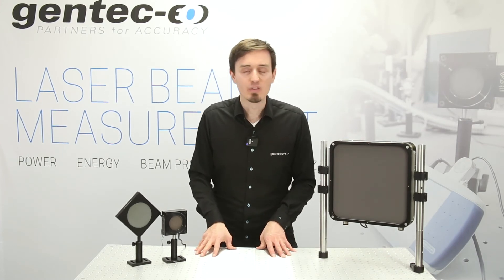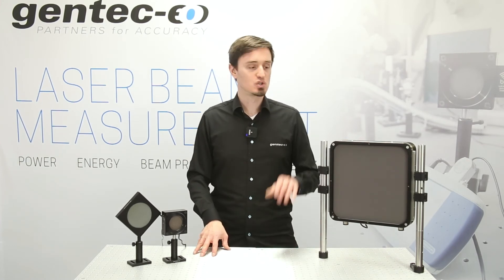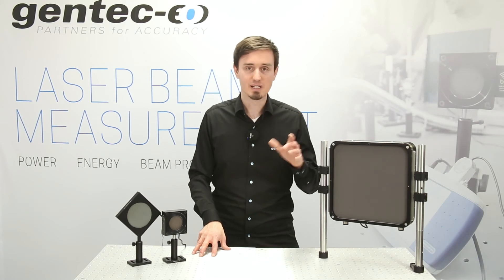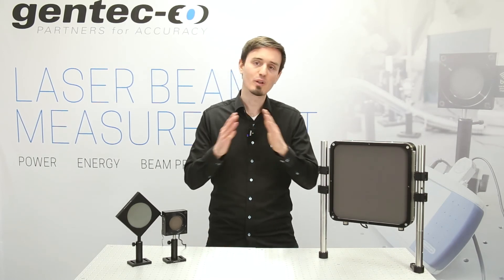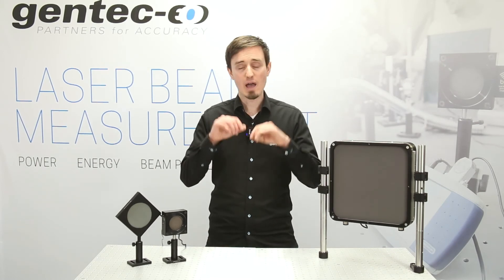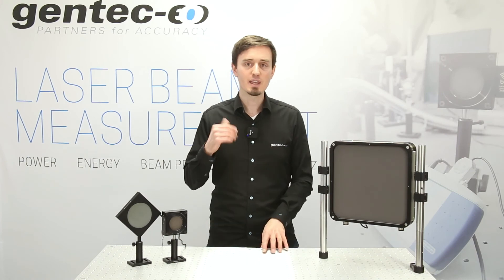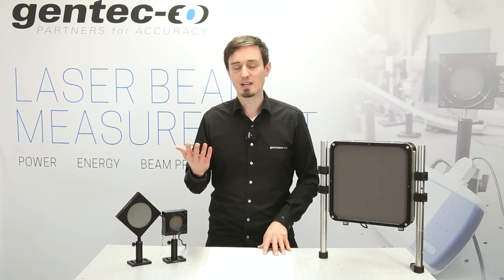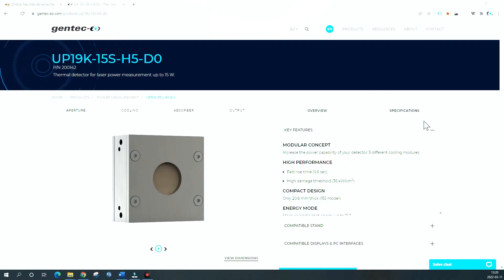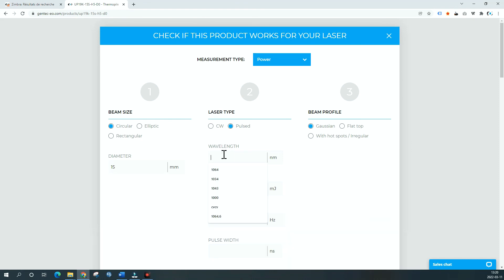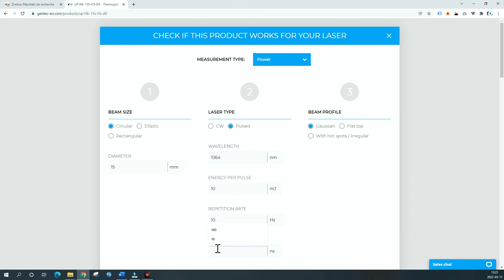The maximum allowed energy density in joules per square centimeter on a given detector is a function of your laser wavelength, pulse width, and average power in watts, and again we do provide guidance for safe use. You may want to check out the application feature on the Gentec EO website, which can help guide you as well.